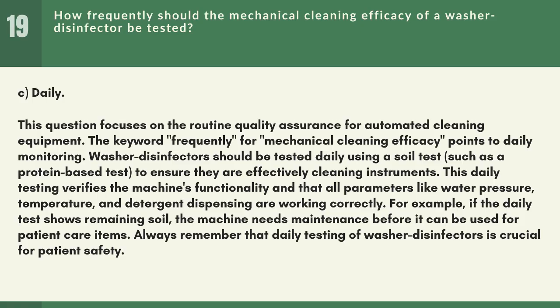This daily testing verifies the machine's functionality and that all parameters like water pressure, temperature, and detergent dispensing are working correctly. For example, if the daily test shows remaining soil, the machine needs maintenance before it can be used for patient care items. Always remember that daily testing of washer disinfectors is crucial for patient safety.